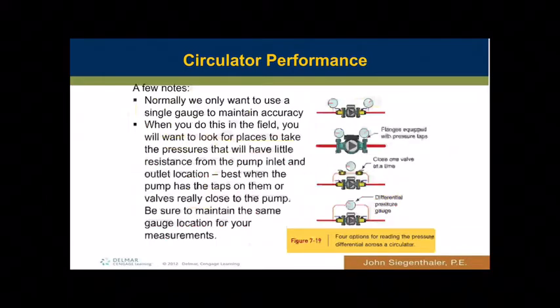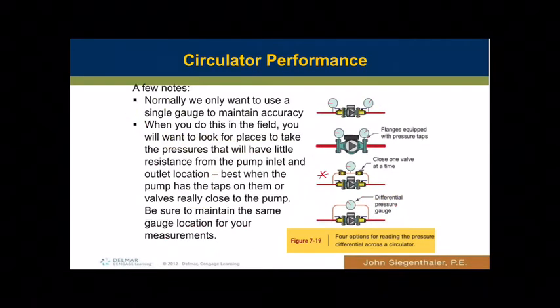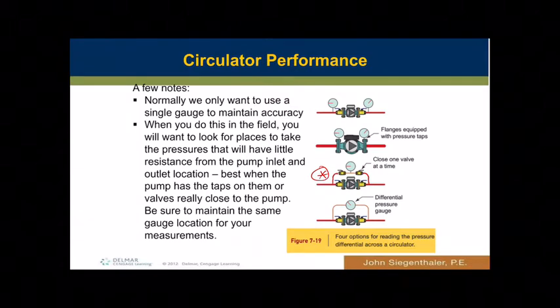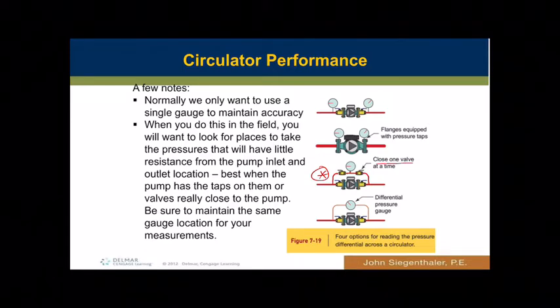Normally you'll want to use a single gauge when doing these pressure differentials. Commercially, we'll often see an arrangement with two valves and a gauge teed off to identify what that pressure is. You close one valve at a time and leave the other open, reading the pressure at the inlet or outlet side of the pump. The difference between those readings is what you're looking for — that's typically the way it's done.